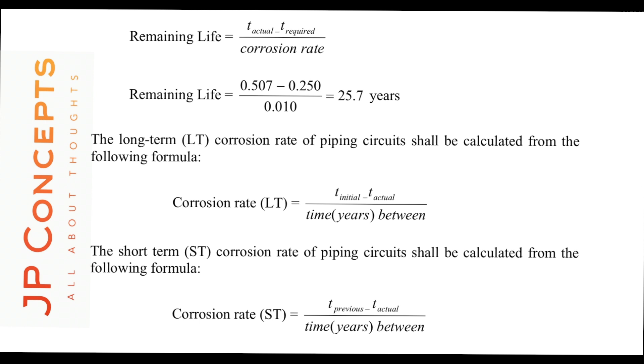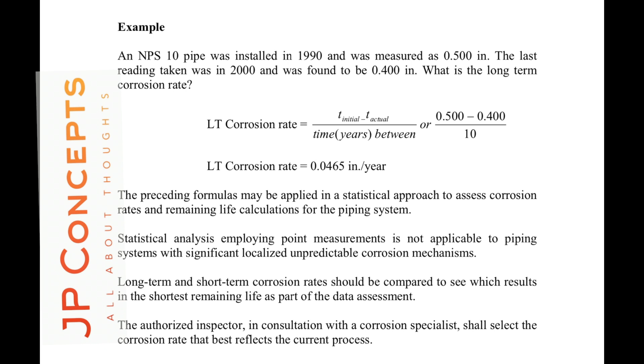Normally, if you have long-term and short-term corrosion rates, they should be compared to see which results in the shortest remnant life, as a part of data assessment. The authorized inspector, in consultation with the corrosion specialist, shall select the appropriate corrosion rate by considering all the conditions and current process. How to approach a new service and what about change in service inspections? For a new piping system and piping systems for which the service conditions are being changed, one of the following methods shall be employed.